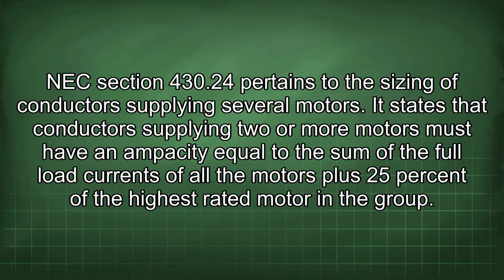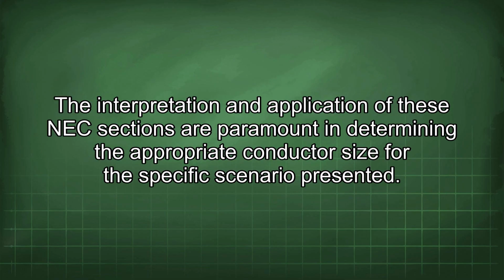NEC Section 430.24 pertains to the sizing of conductors supplying several motors. It states that conductors supplying two or more motors must have an ampacity equal to the sum of the full load currents of all the motors plus 25% of the highest rated motor in the group. The interpretation and application of these NEC sections are paramount in determining the appropriate conductor size for the specific scenario presented.